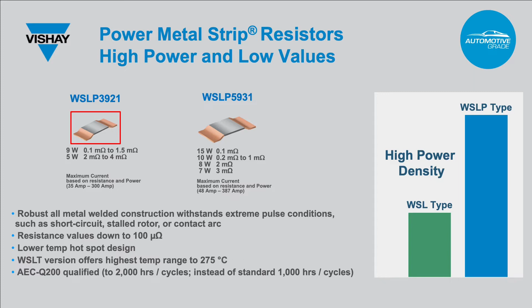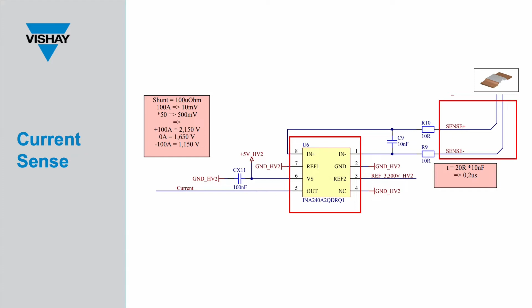Now, back to how the differential voltage measured across the current shunt is processed. Here's a detailed view of the current sense amplifier that was used to take the very small voltage in millivolts and amplify it to a voltage level that can be used for control and protection. In this case, that amplified voltage is fed into both the microprocessor for current monitoring and also into the comparator circuits, which I'll get to shortly, used for the overcurrent detection and short circuit shutdown.